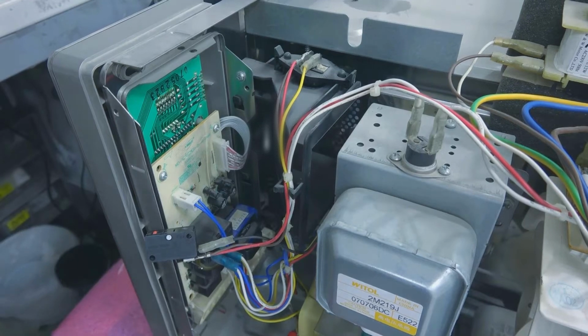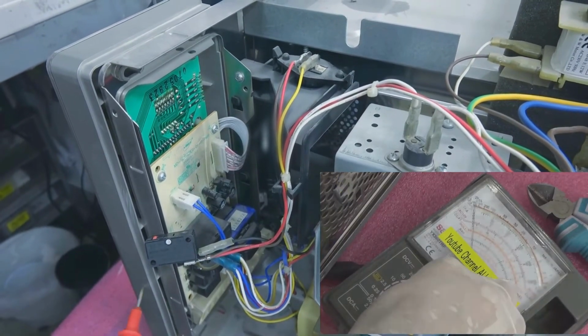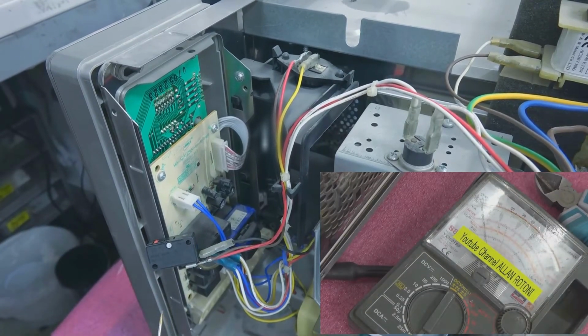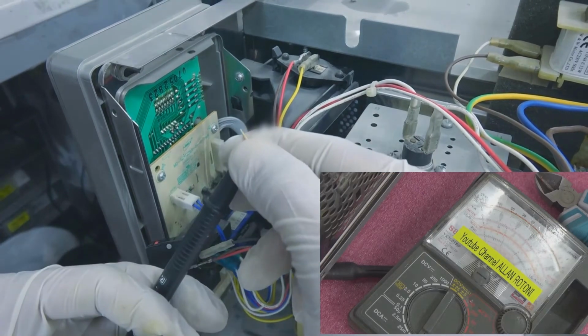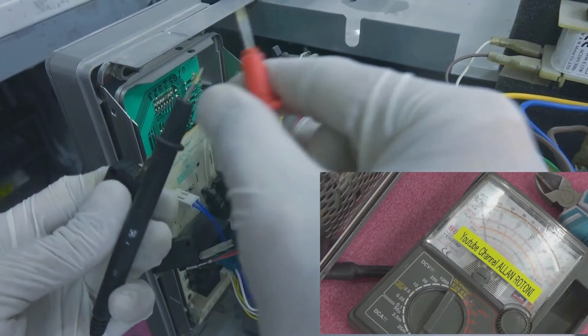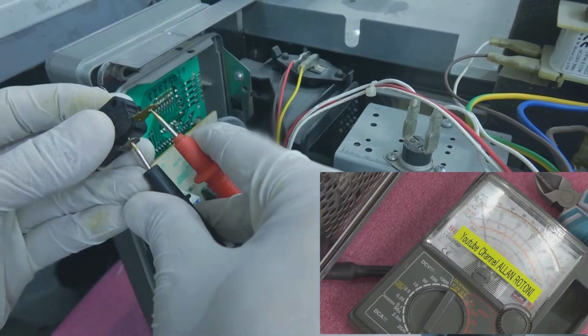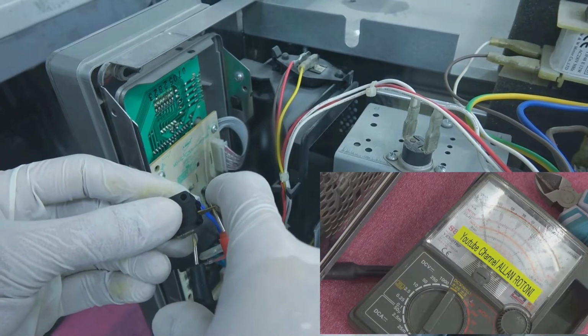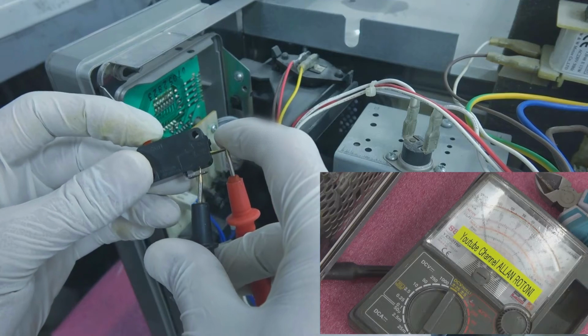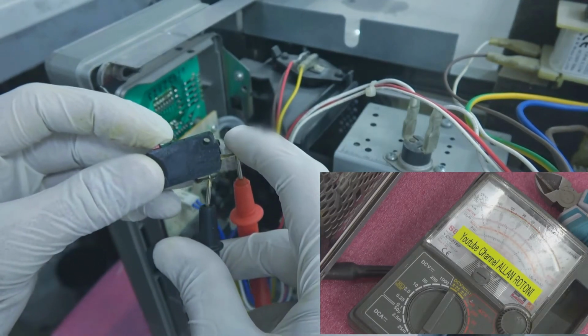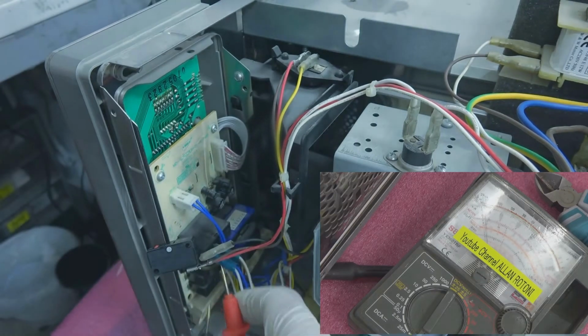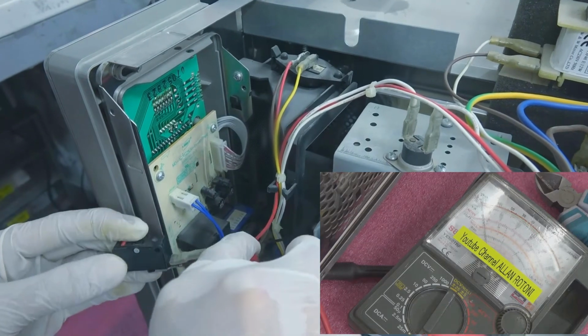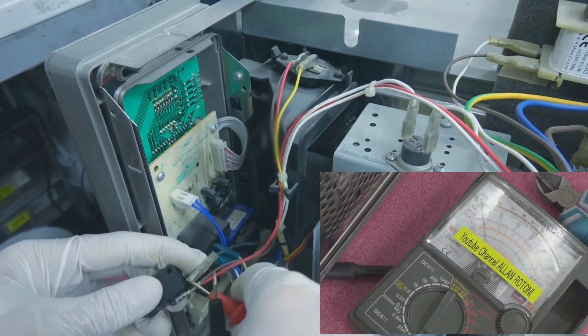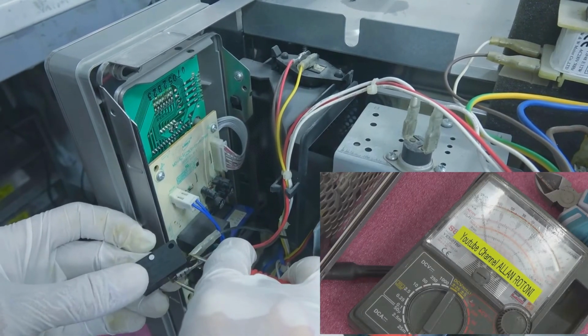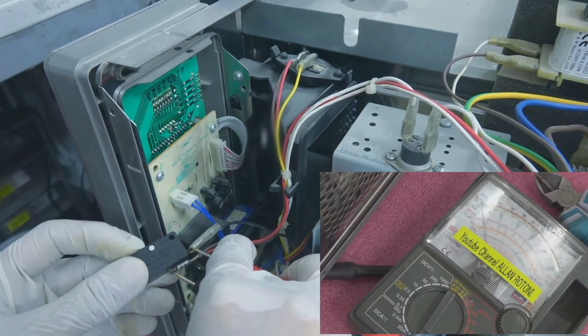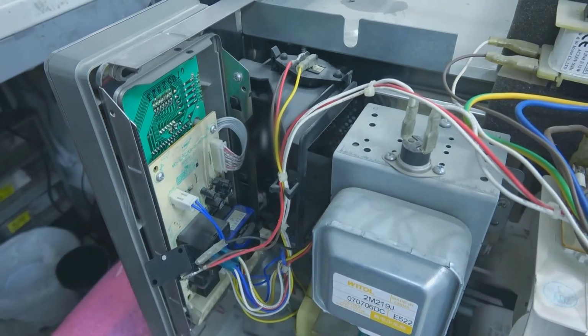How to test this one? It's just like a switch. I will set my meter mode on ×1 just to check the continuity. Okay. This one is normally open. Normally open, no continuity. When I push this one, it has continuity, meaning this one is working fine. How about this one? Check this one, and it's open, no continuity, and this one is not moving. We have to replace it and test again the unit.